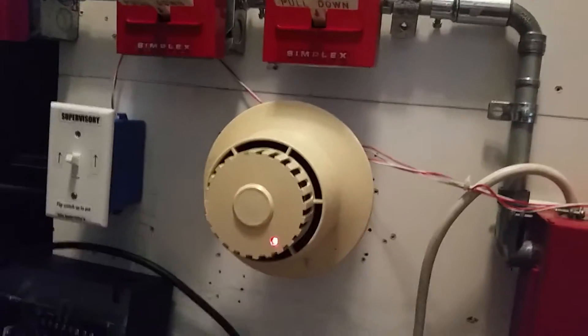I have to demonstrate the smoke detector, so let me find my magnet and I'll be back. Alright, I'm back and I have my magnet. This thing has magnet test. Garrett didn't get the smoke detector to work, but I did. You'll see it blink twice and then go steady. There it goes. Now I'll reset the pull station — lucky me, because I got all the same key. They're all B keys since they're all Simplex T-bars.